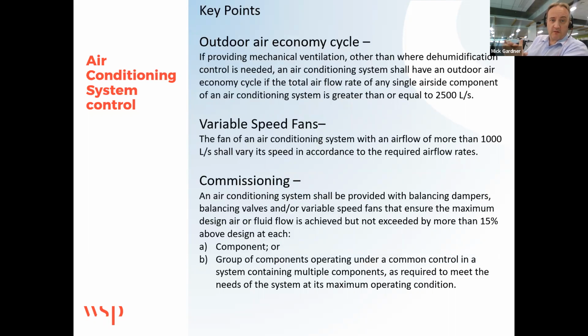So outdoor air economy cycle, as you know, has to be provided more than 2.5 meters cubed, other than where humidity control is required on an air conditioning system. Variable speed fans, again, required for anything over 1,000 liters a second. I think that's going to be an interesting one at the moment. I know there's a lot of issues with availability of fans and control, so we'll see how that goes at the moment. And commissioning, an air conditioning system should be provided with dampers for balancing. Also, variable speed fans ensure the maximum design air or fluid flow is achieved, but not exceeding more than 15% above the design. So, yeah, we can't greatly oversize pumps and fans and just throttle things down and turn them down as we probably have done in the past.